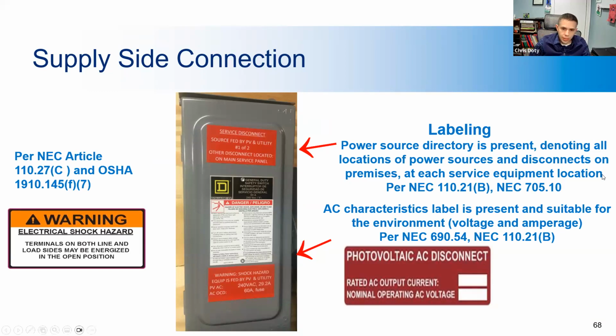All right, so here we have examples of labeling requirements for this type of connection. You have the traditional electrical shock label right here, and the PV disconnect label right here that you would normally see. You also have the disconnect label here that shows where the disconnects are for the main breaker essentially, and the PV disconnect. The PV part of the code probably has the heaviest requirements for labeling that there is, and it's all important to maintain the safety of the system. So definitely familiarize yourself with that part of the code to ensure that these are installed safely and you know what you're looking at.